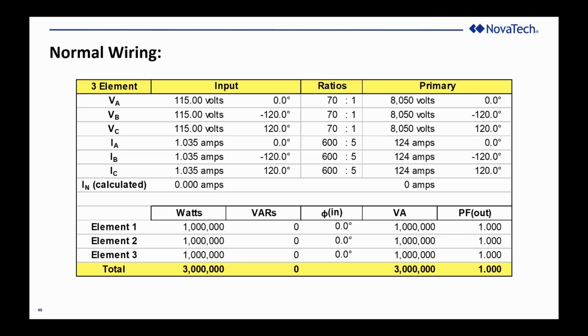And what I've done for the purposes of this demonstration is I simply picked out an amount of current that will cause the power to add up to 3 megawatts. It's a 3-element meter, so 3 megawatts, 1 megawatt per phase. It's just illustrative. All the vector math is being done in the background. That's not the point of this presentation. The point of this presentation is to show you what happens when I do this.